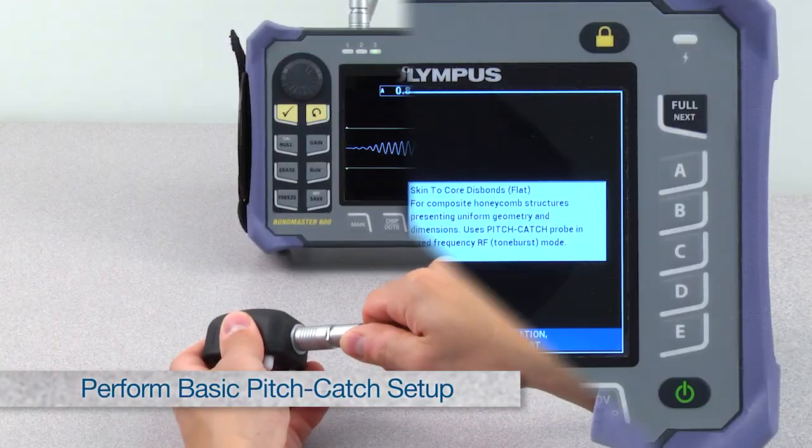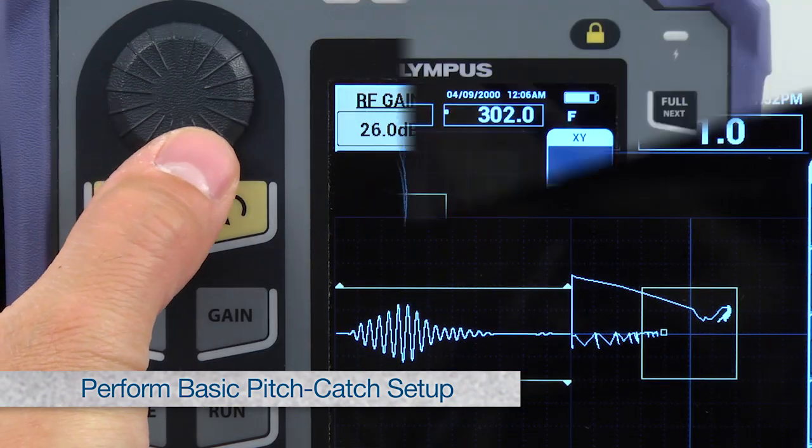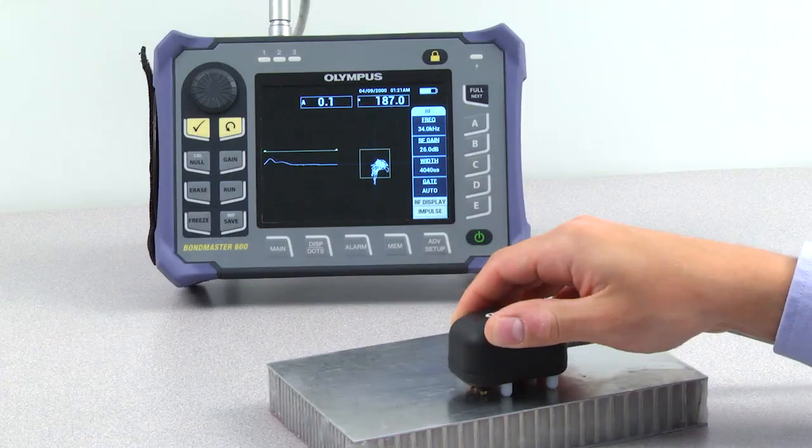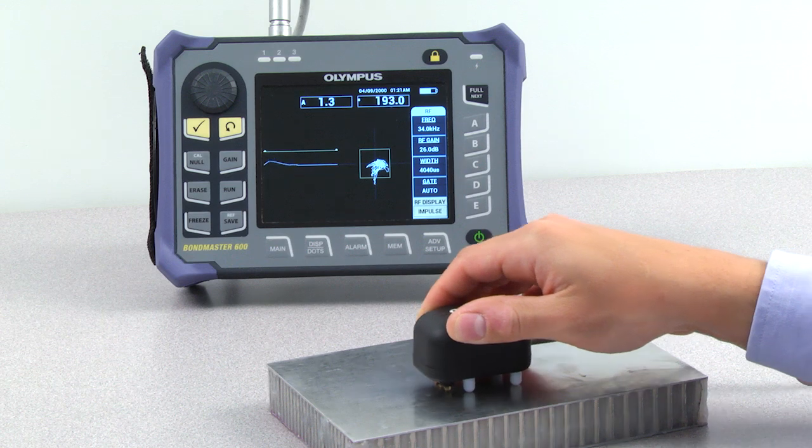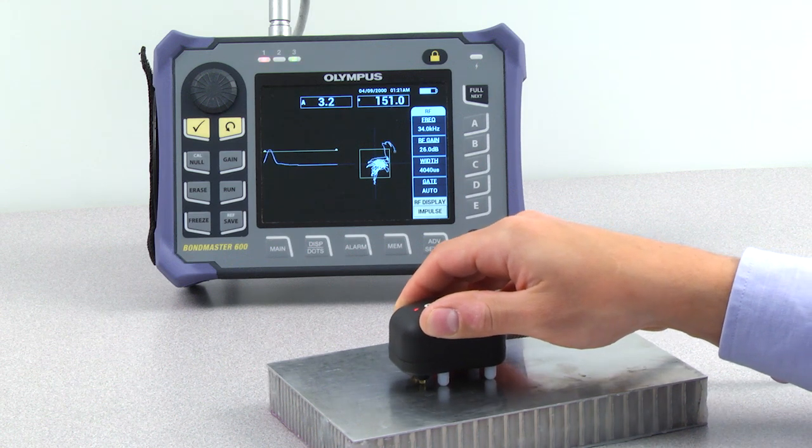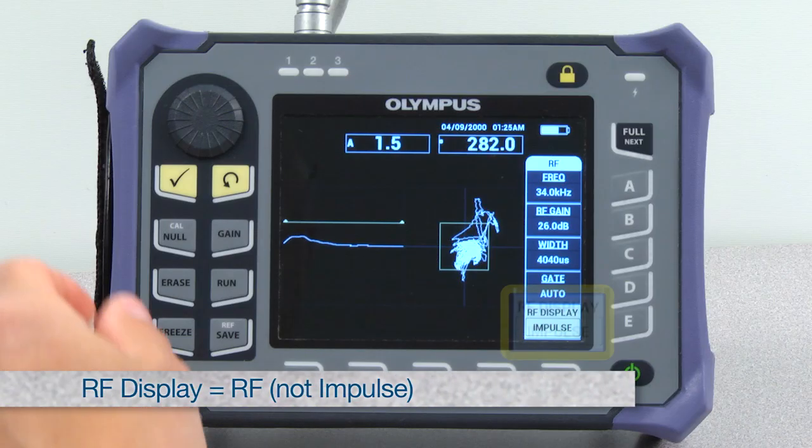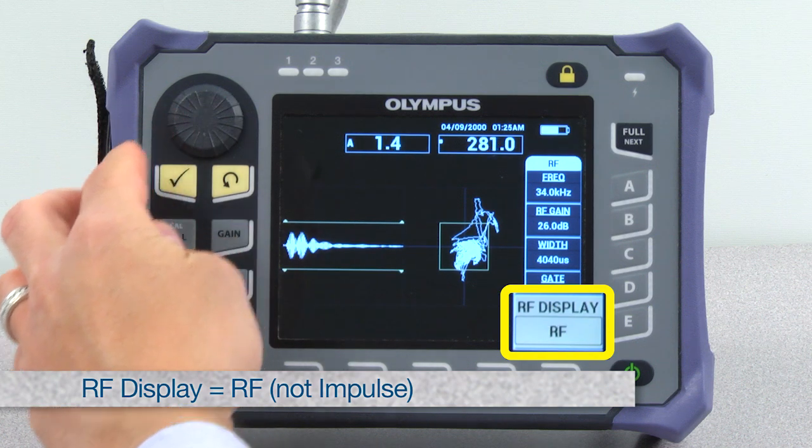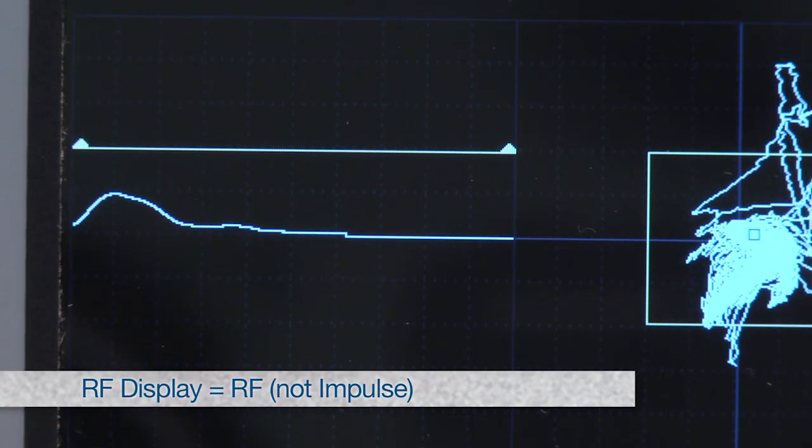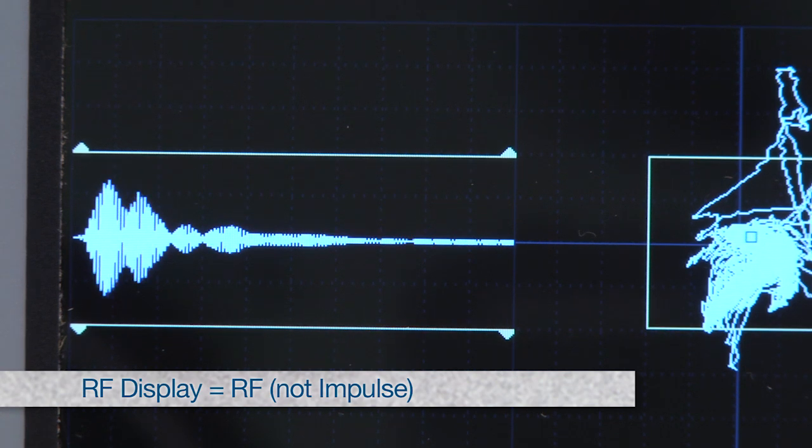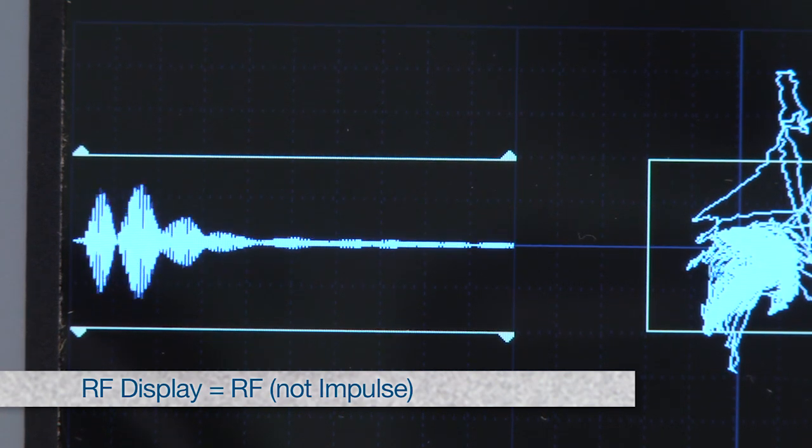First, perform a basic pitch catch RF setup as explained previously in this video. If you believe you have finished, but the signals do not look satisfactory, follow these steps. Make sure to display the RF signal as RF and not impulse. The RF display is preferred as each signal oscillation can be seen.